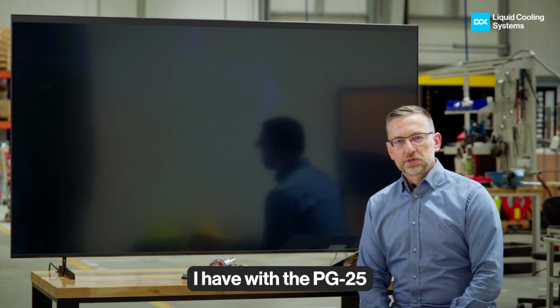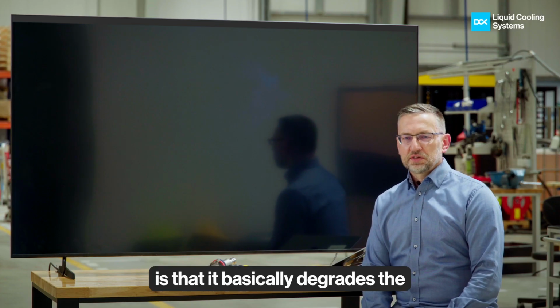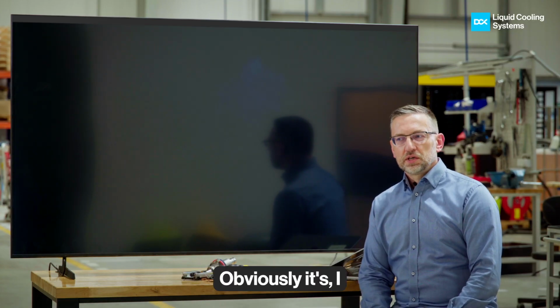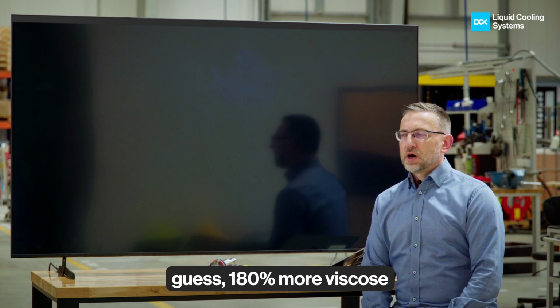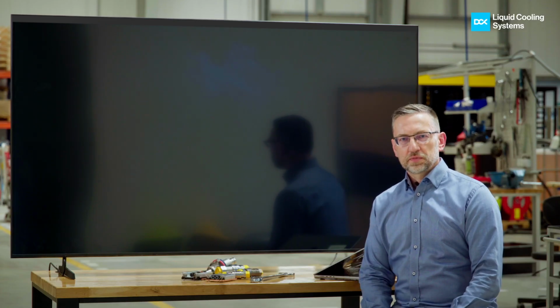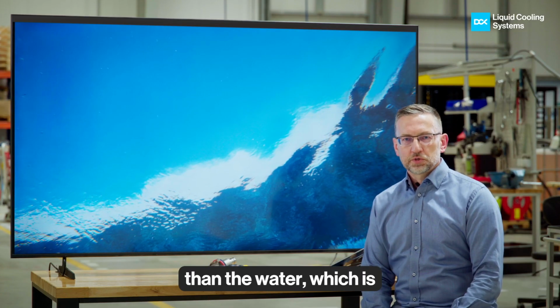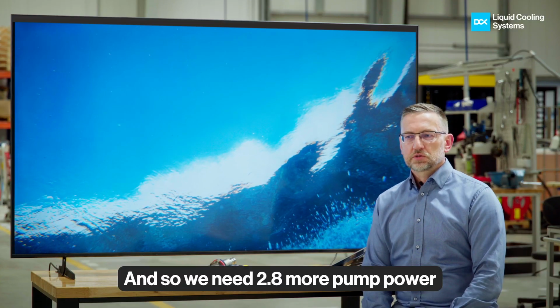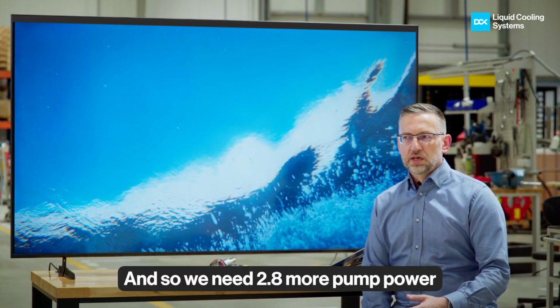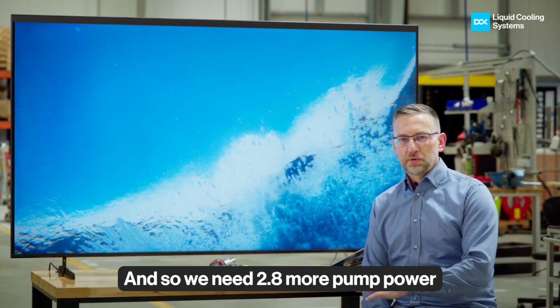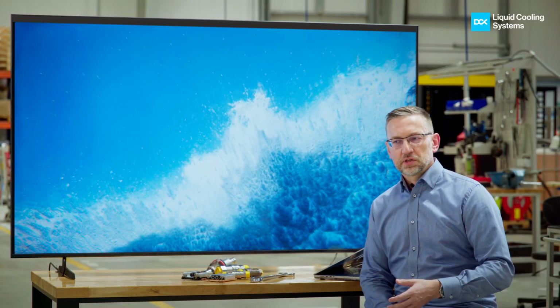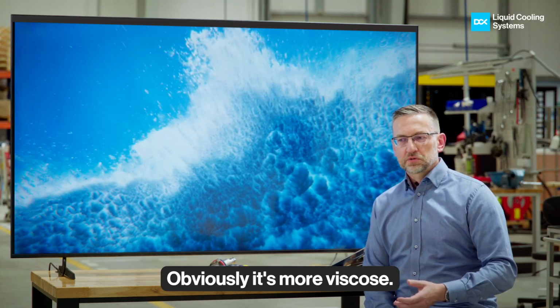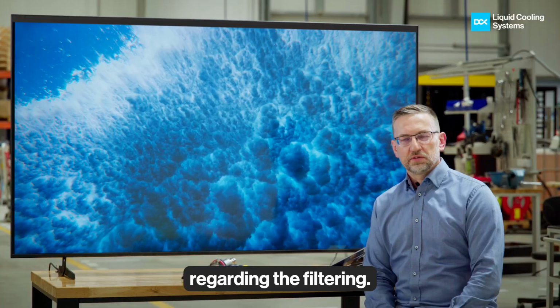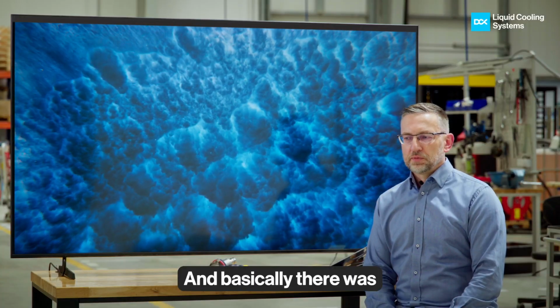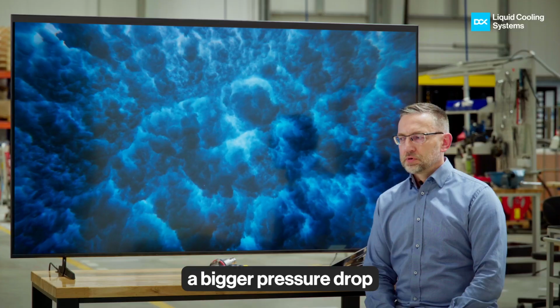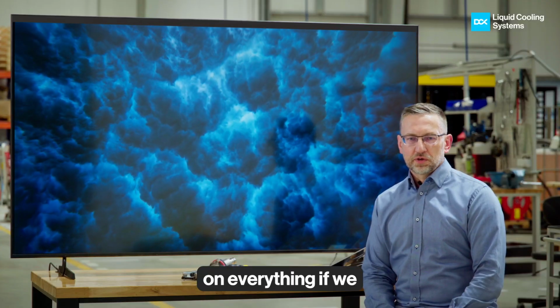The second problem I have with PG25 is that it degrades efficiency significantly. It's about 180% more viscous than water, which is the best coolant on the planet. So we need 2.8 times more pump power to circulate that fluid. Being more viscous also creates additional challenges regarding filtering, and basically a bigger pressure drop on everything if we use such a coolant.